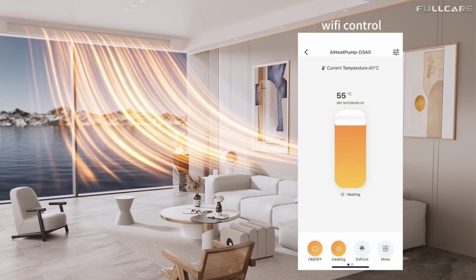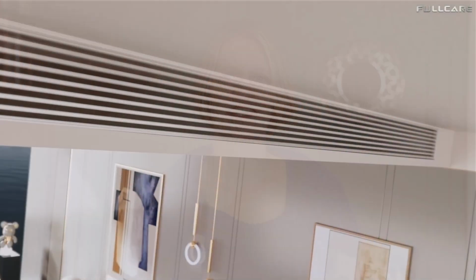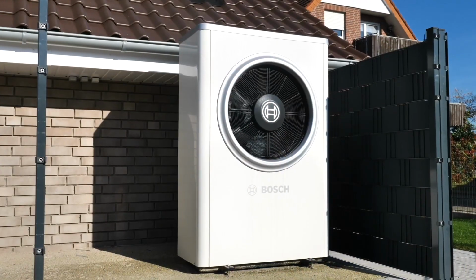as dehumidifiers. A properly sized system will constantly pull moisture from the air in areas of high humidity, leaving you comfortable and your home mold-free. An oversized system will spend most of its time off, allowing moisture to build up. Even if you live in a dry climate, an oversized system will result in a less comfortable home. The more time a heat pump runs, the more time it has to distribute warm or cold air through your home.